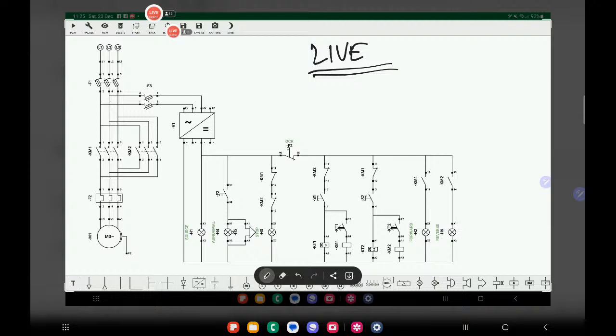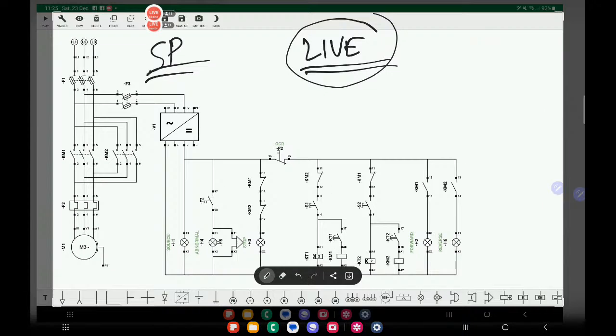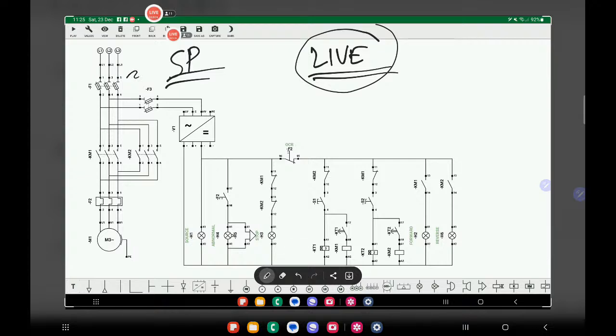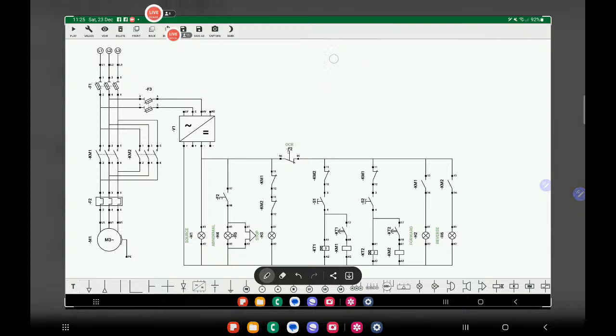So I prefer to fix the circuit in a live condition. Let's say you suspect single phasing on one of the systems, on the F1. The easiest way is I don't need to drop off the main supply from L1, L2, L3, then push the F1 and measure the continuity of each line. That would be the condition when you're testing it as a dead circuit. But in a live circuit, it's just too easy, right? Let's say it is a 440 volts AC.